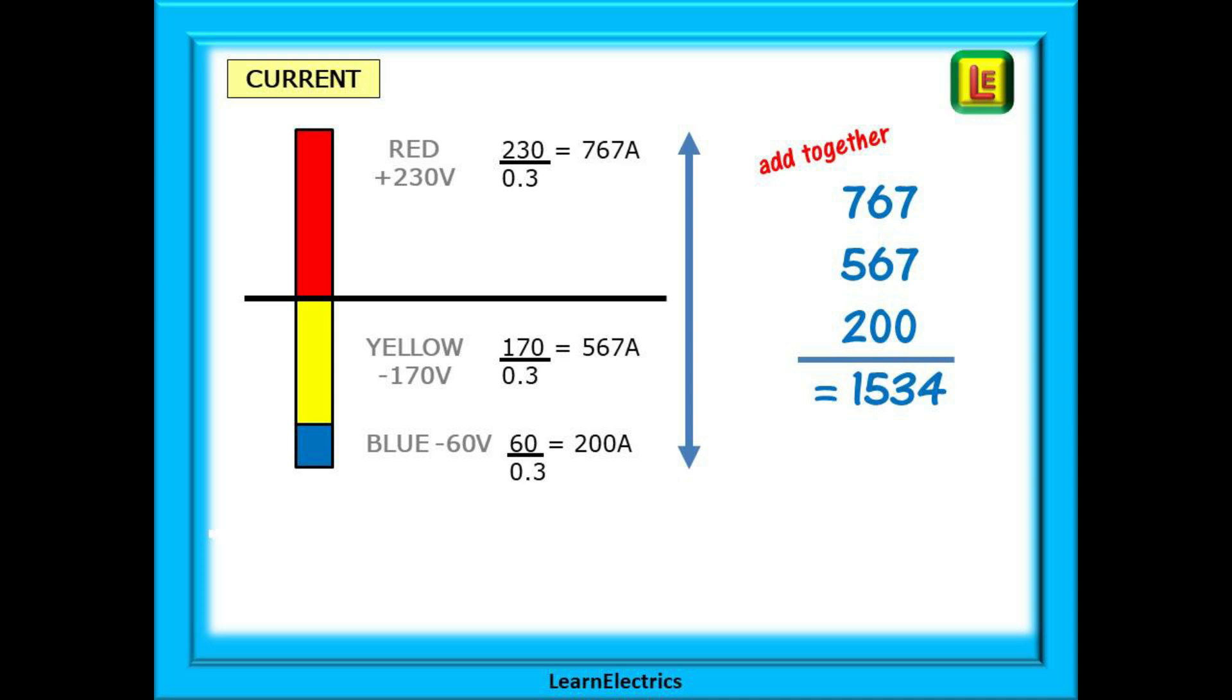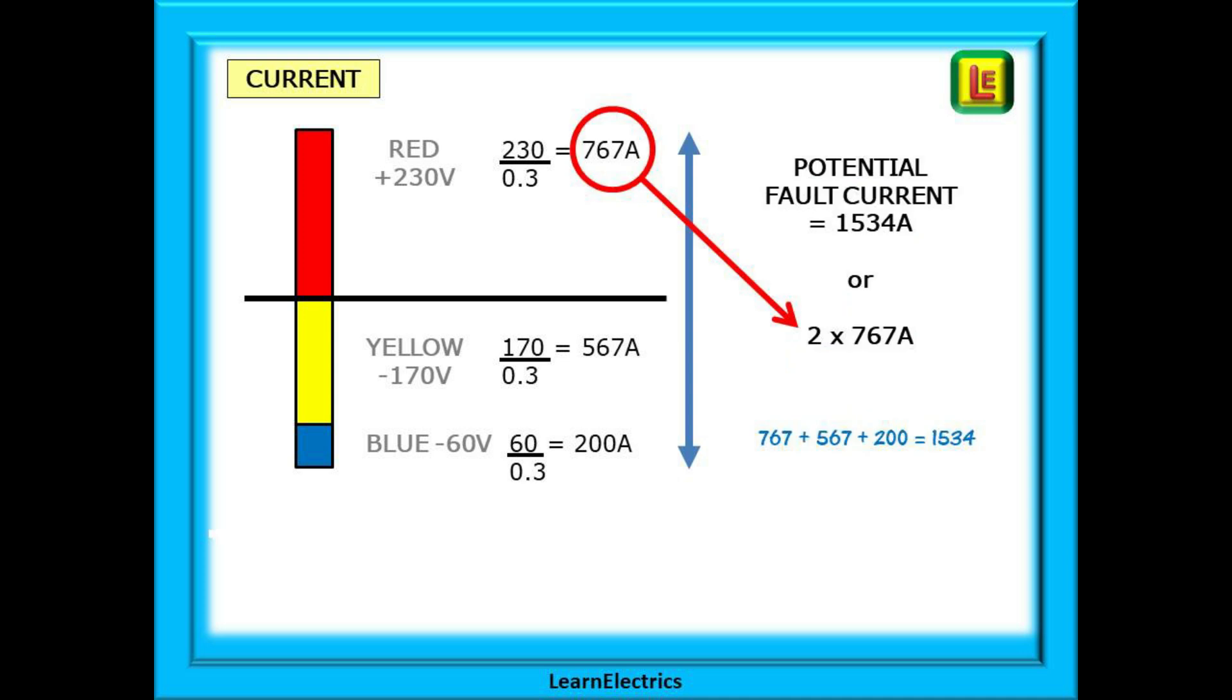767 plus 567 plus 200 is 1534 amps. 1534 amps is the same as 2 times 767. For a short across all three of the phase conductors at the same time, measure the single phase live to neutral fault current between live and neutral and then multiply by 2. Easy.